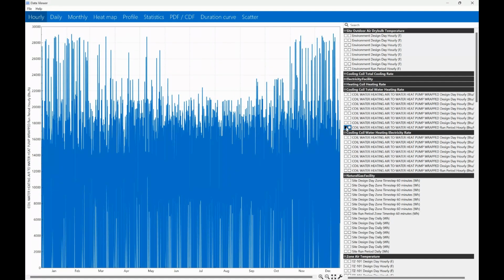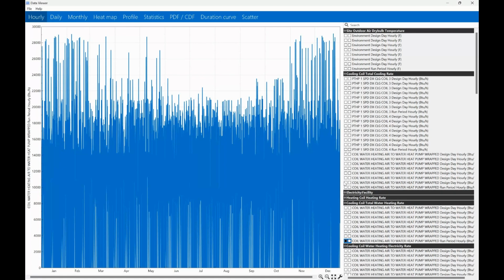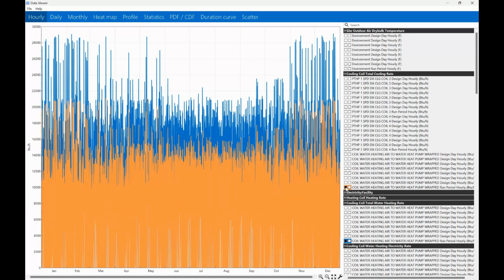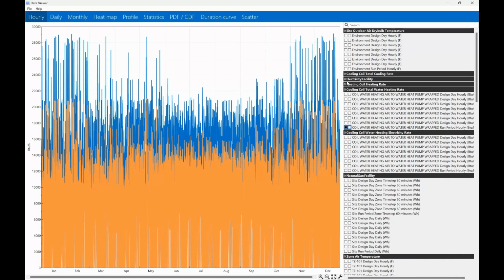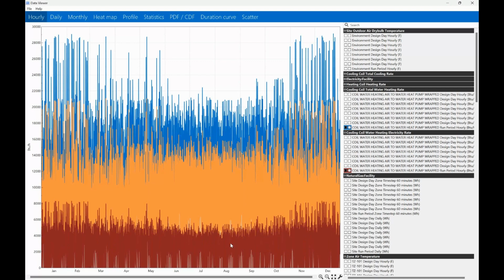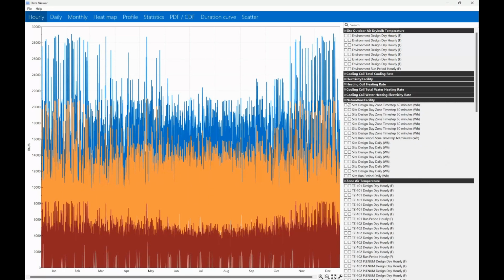So here's our compressor, and this is the BTU rate that the compressor is putting out. The next one, let's do the evaporator, and we're going to do the run period for this. This is basically the heat that the evaporator is taking from the apparatus bay. And then we have the compressor electricity rate right here, so here's our compressor electricity energy. If you add the compressor energy to the evaporator energy, you should get the total heat that we're getting from the apparatus bay.